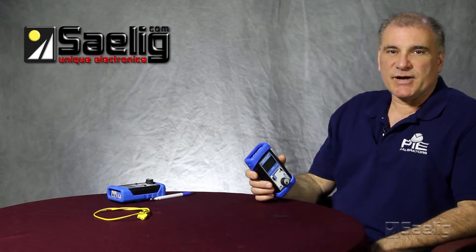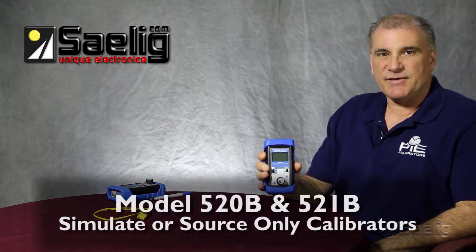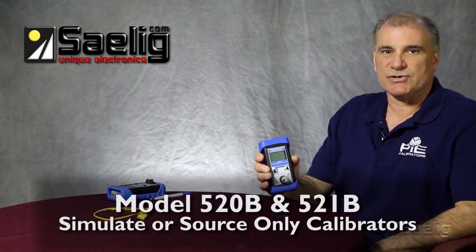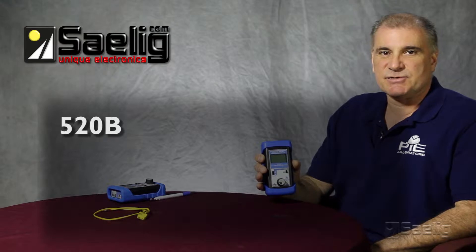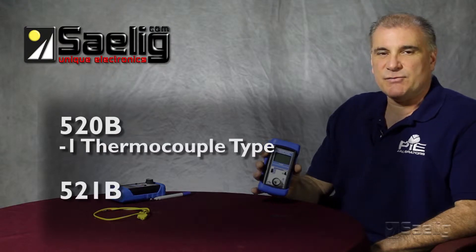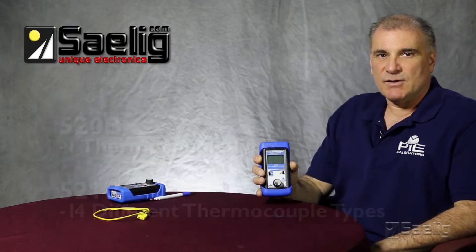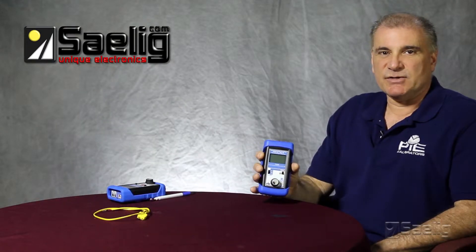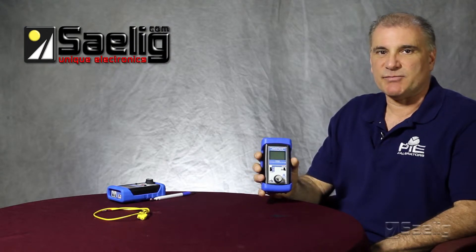We have four calibrators in the thermocouple only line. The 520B and 521B are simulate or source only calibrators. The 520B is set up to one thermocouple type only, while the 521B is set up for 14 different thermocouples. They also both will simulate the millivolt voltage that corresponds with the thermocouple type and temperature set point.